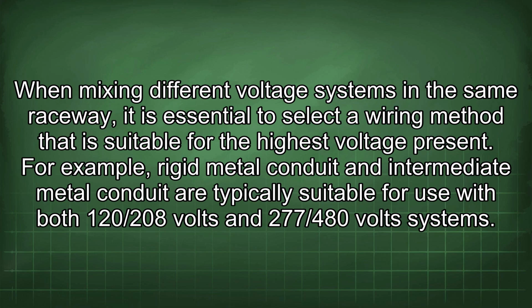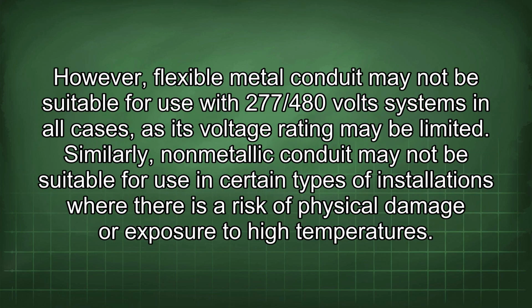For example, rigid metal conduit and intermediate metal conduit are typically suitable for use with both 120/208 volt and 277/480 volt systems. However, flexible metal conduit may not be suitable for use with 277/480 volt systems in all cases, as its voltage rating may be limited. Similarly, non-metallic conduit may not be suitable for use in certain types of installations where there is a risk of physical damage or exposure to high temperatures.